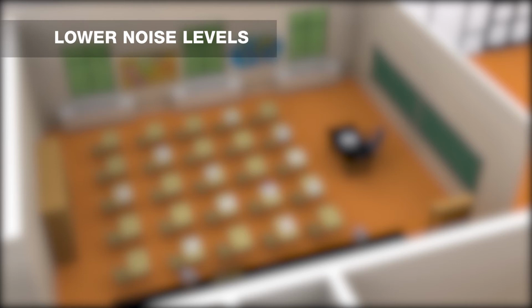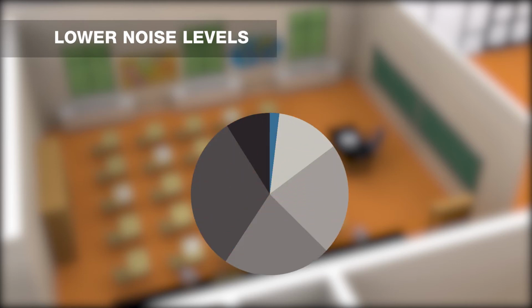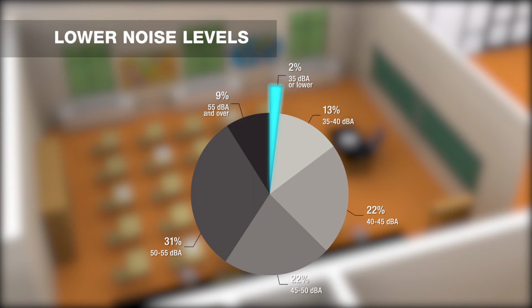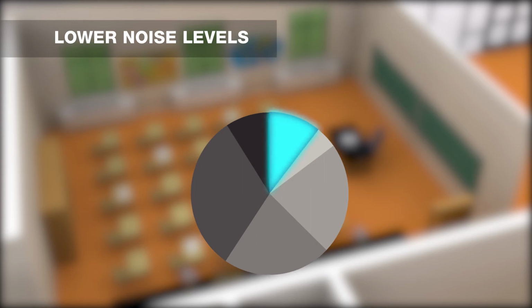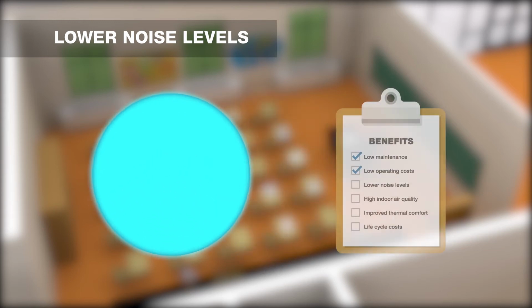ANSI S12.60 2012 states that background noise levels in all core learning areas should not exceed 35 dBA. According to a recent study, only 1 out of 54 classrooms met this standard. This leaves almost no room to add noise from an HVAC system. The displacement beam has no moving parts, and they release air slowly, making them inherently very quiet.